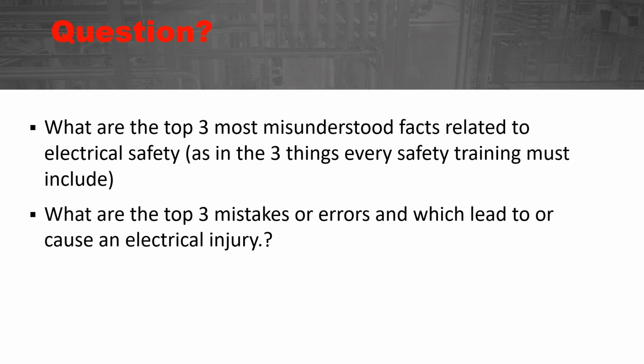And Fluke makes a product. Now, I don't sell any of these products, but when I find products that I like and that I know are great for electricians and maintenance people out there, then I'm going to show them. Fluke makes what they call a proving unit, and this proving unit has 2 contacts where you use this to test your tester. And it's AC or DC, it's 4 AA batteries. You test your tester to make sure the tester is working.